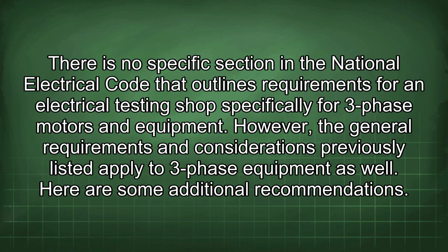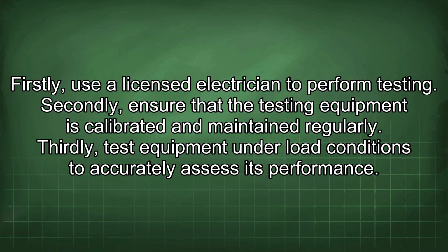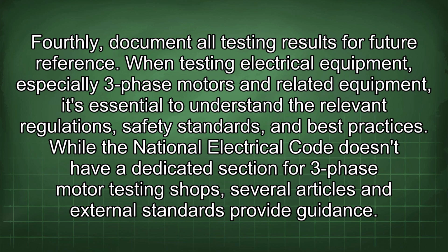There is no specific section in the National Electrical Code that outlines requirements for an electrical testing shop specifically for three-phase motors and equipment. However, the general requirements and considerations previously listed apply to three-phase equipment as well. Here are some additional recommendations. Firstly, use a licensed electrician to perform testing. Secondly, ensure that the testing equipment is calibrated and maintained regularly. Thirdly, test equipment under load conditions to accurately assess its performance. Fourthly, document all testing results for future reference.